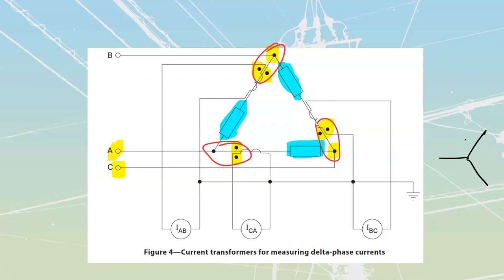There is another error inside of here, on one of my connections for this Y point. If you take a look at the Y points, what we should have is the same line of each of my CTs connected. Here's the dots, and the tail end connects to my Y point. Here's the dots, the tail end connects to my Y point. Here's the dots, and oh my goodness, it's the dot end that's connected - this is a wrong connection. Ignore that one; it should be the tail end over here that is the actual connection. Make that correction inside of your book.